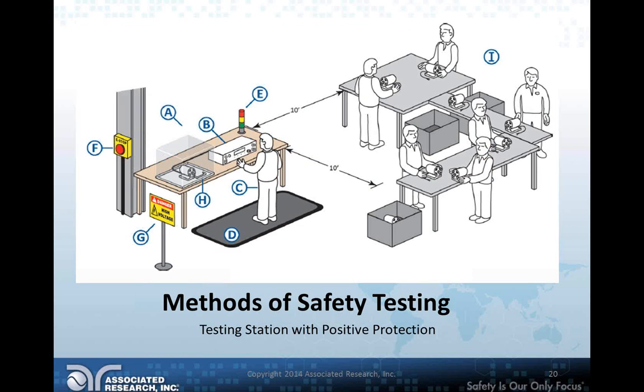This is kind of what my lab looks like, aside from the production floor off to the right-hand side of the image there. So a couple things to notice here. When I say positive protection, what I mean is the operator cannot contact the device under test while it's testing. As you can see where it's labeled A in the picture here, what that's meant to show is an enclosure over our device under test. You can see there's a motor labeled H there. So we're just testing a motor here. B is our high pot tester, or dielectric withstand tester, and A is an enclosure.